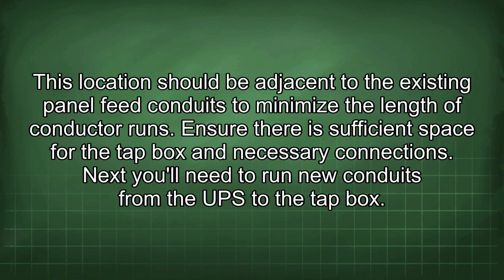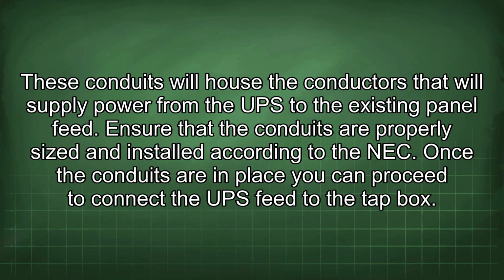Next, you'll need to run new conduits from the UPS to the tap box. These conduits will house the conductors that will supply power from the UPS to the existing panel feed. Ensure that the conduits are properly sized and installed according to the NEC.